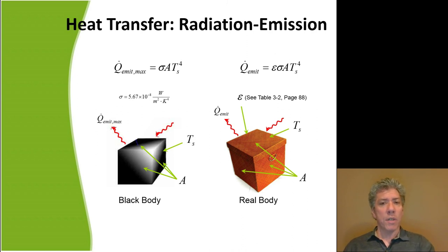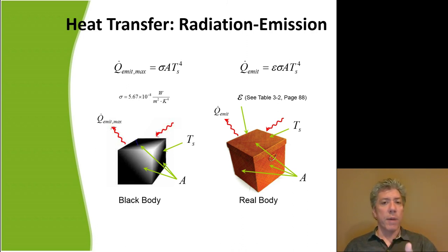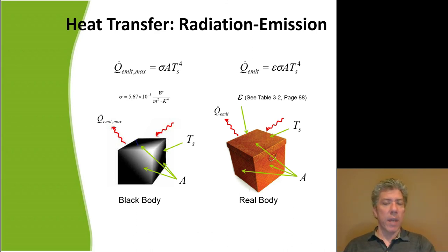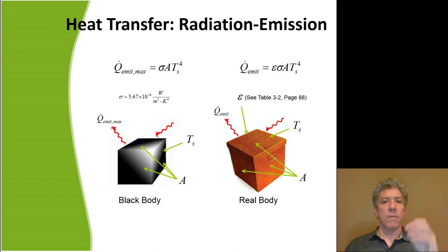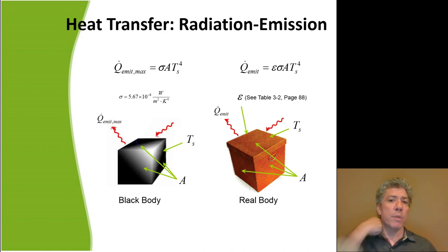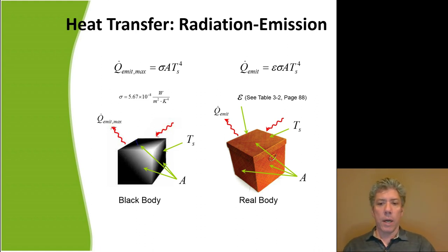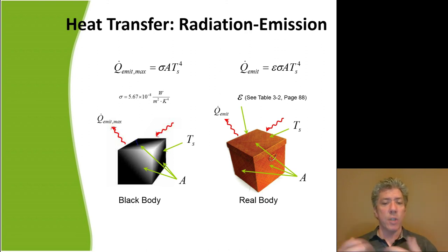The reason is that infrared thermometer assumes a relatively high emissivity of about 95%, whereas the emissivity of galvanized pipe was more like 10% — 0.1. The emissivity varies between about 0 and 1, with 1 being a perfect black body. Real bodies do not emit radiation at as high a rate as you would theoretically expect because they're not black bodies — and by the way, there's no such thing as a black body.